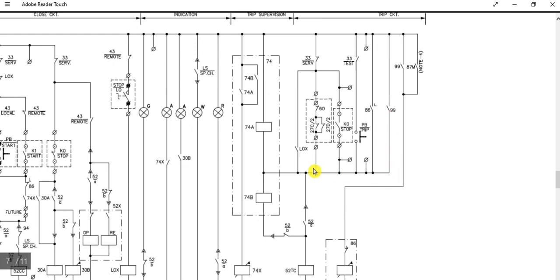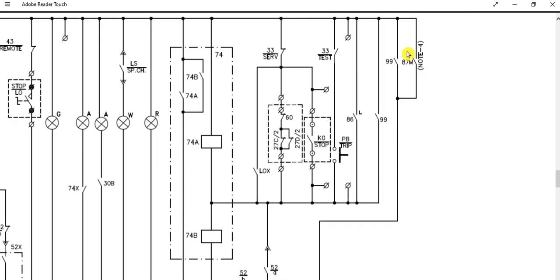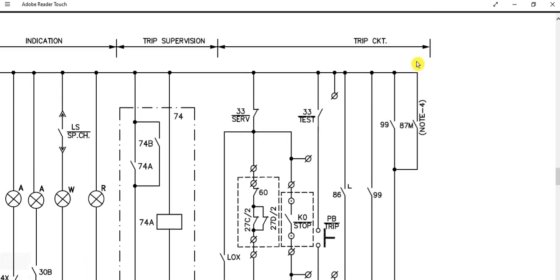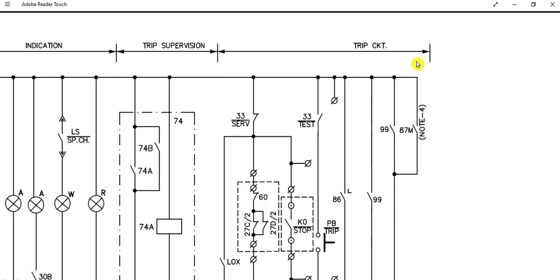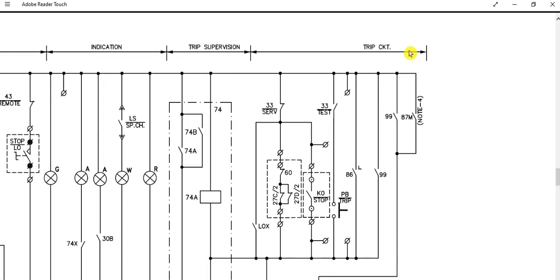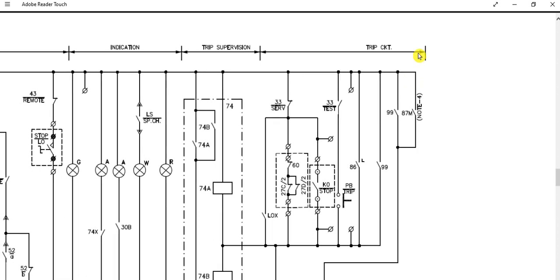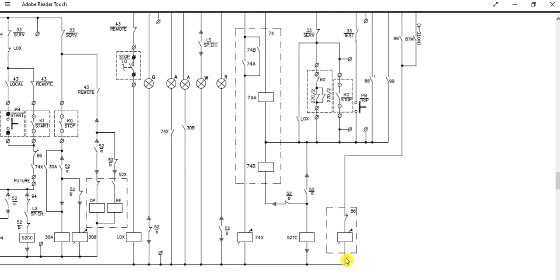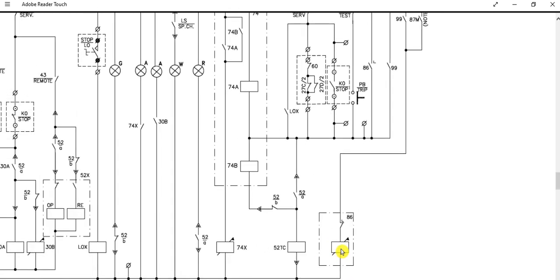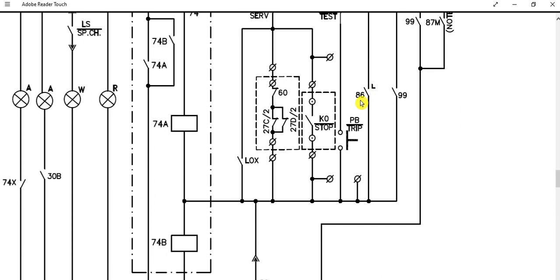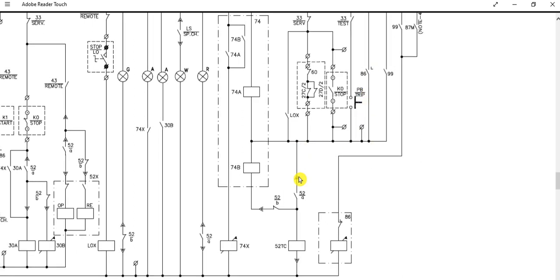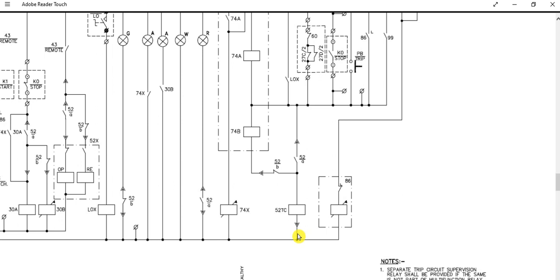Relay 99 is the main motor protection relay (MPR) — if any protection feature operates, it will also trip the circuit breaker. Relay 87M is the differential motor protection relay — this is applicable for motors rated one megawatt and above. If 87M operates, it will trigger the 86 lockout relay, which will close the 86 relay contact and energize the trip coil of the circuit breaker, causing the breaker to trip.